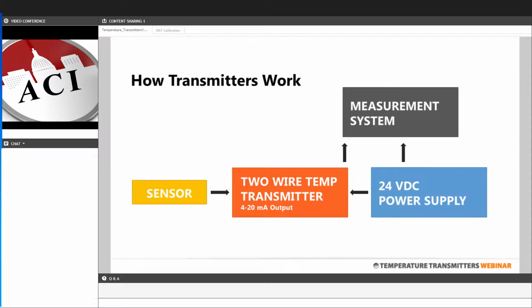A temperature transmitter is a pretty simple device. It works by converting an input from a temperature sensor. In our case, we use a 100 ohm or 1000 ohm platinum RTD, and the transmitter board converts that resistive signal to a 4 to 20 current output back to your BMS or measurement system. Our boards are powered by a 24 volt DC power supply to deliver a 4 to 20 linear current output back to your system.